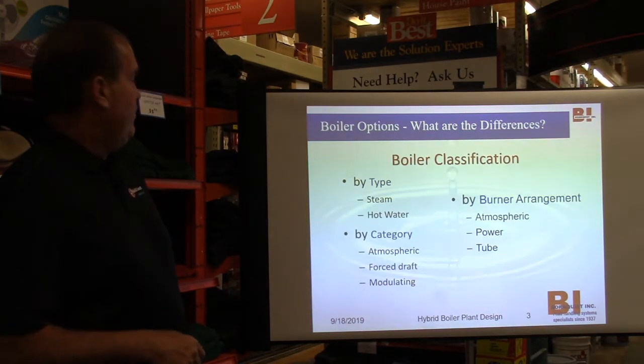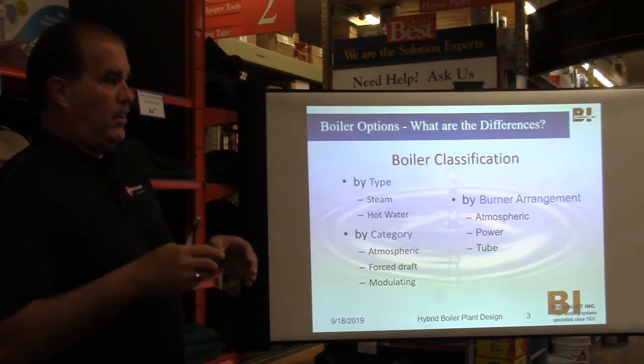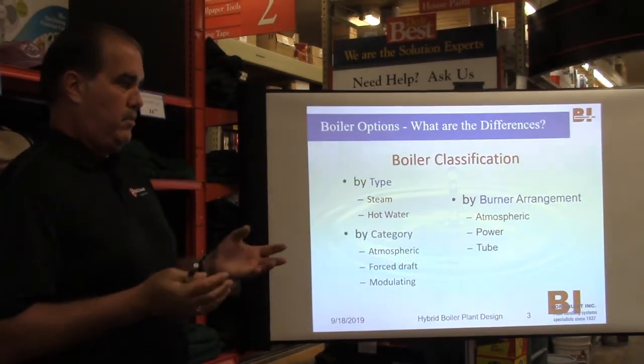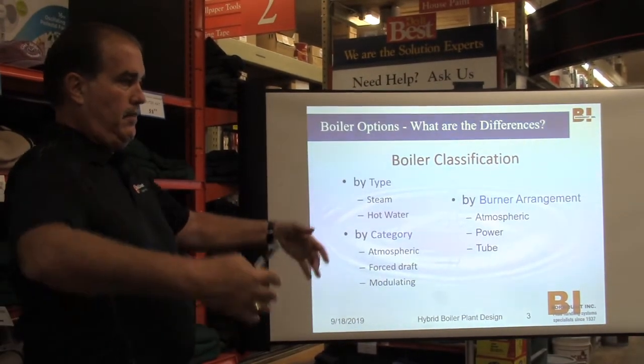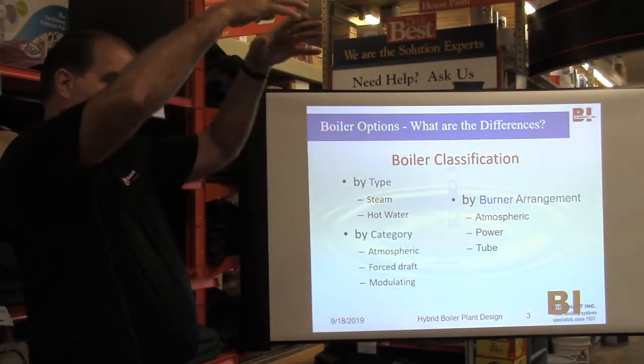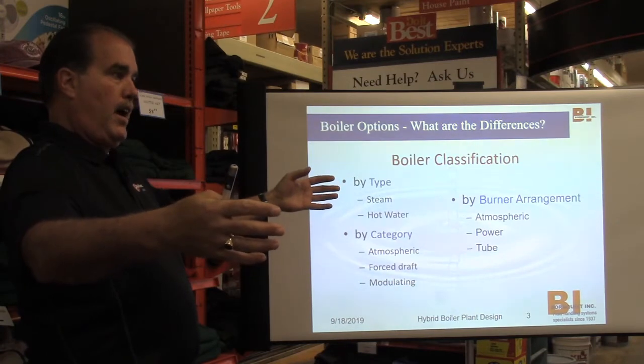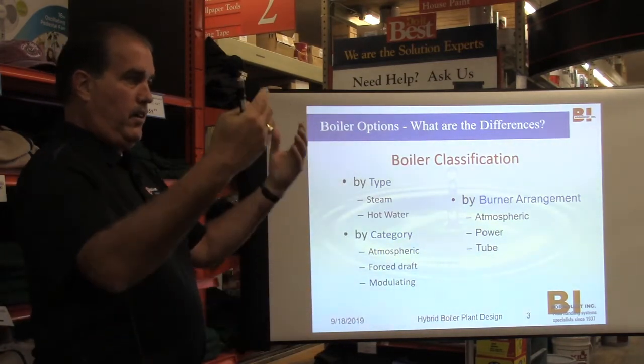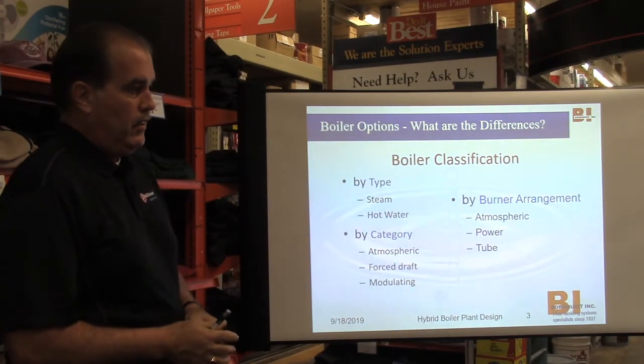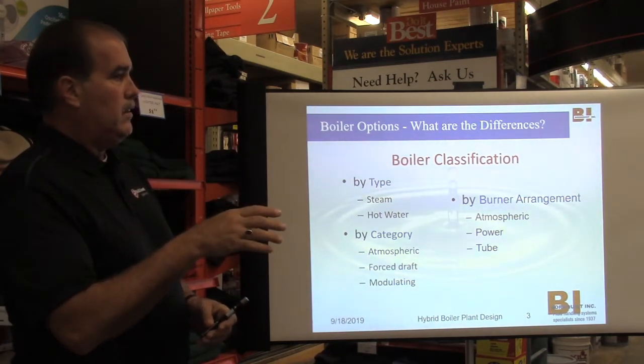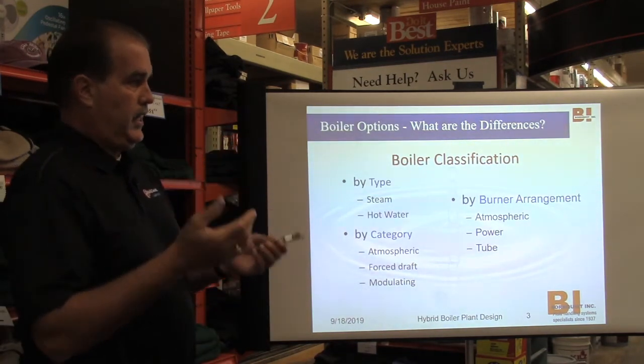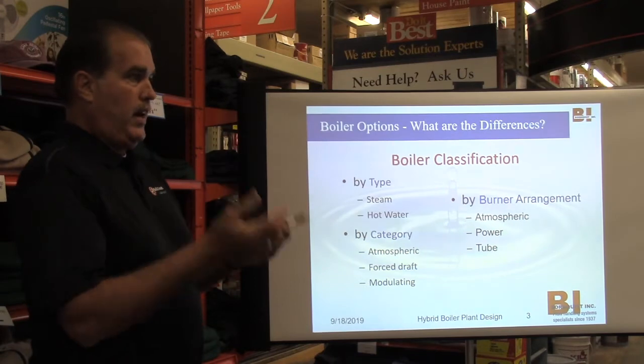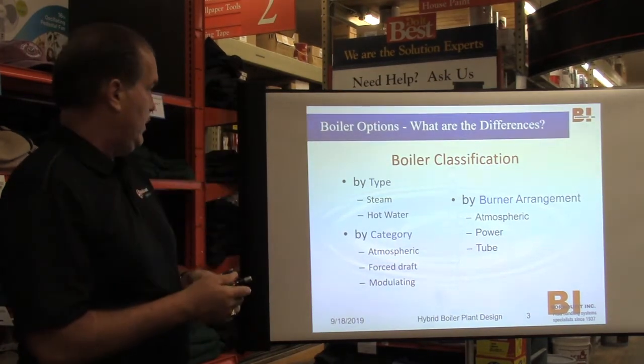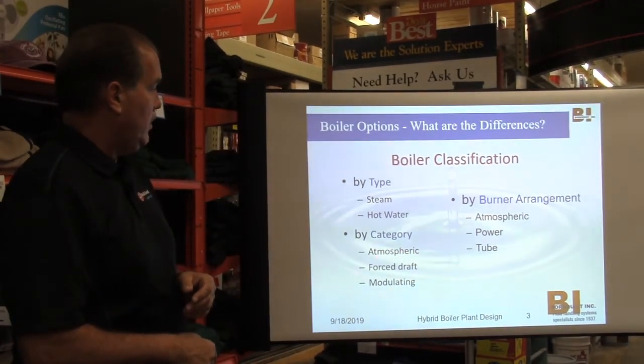Category of boilers. Atmospheric is your typical boiler that you're probably going to see in a residence where the flame's underneath. They have the big hood. Sometimes there's a big bell cap on top of it for the excess air to get pulled up to the chimney. There's no fan blowing on the boiler. It's just a natural lifting of the heated air, that flue gas, that actually pulls the flue gas up and out of the building. That's called an atmospheric boiler.